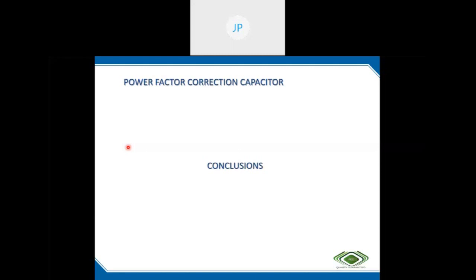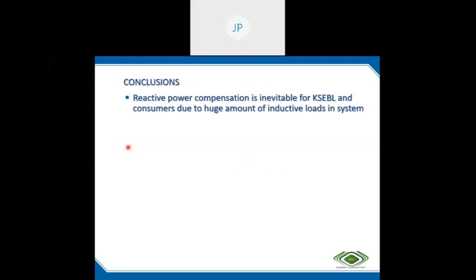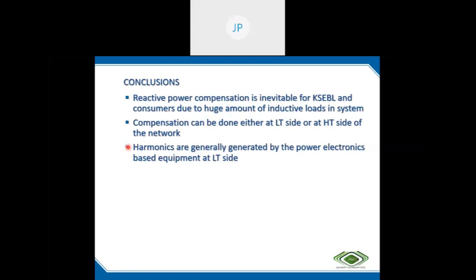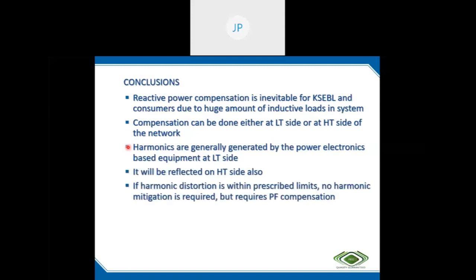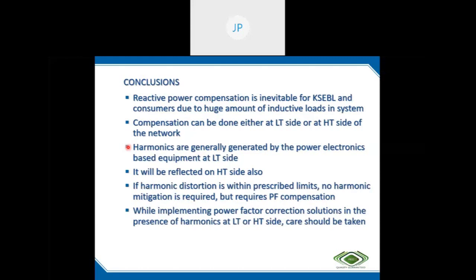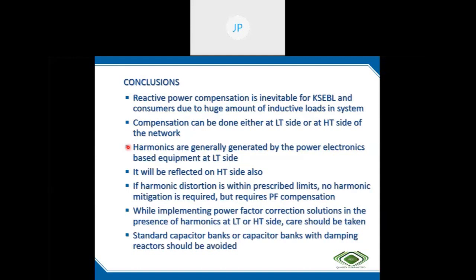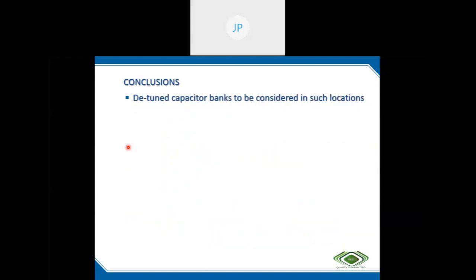Our conclusions are: reactive power compensation is inevitable for KSEB and the consumers due to the high amount of inductive loads in the system. Compensation can be done either at the LT side or HT side of the network. Harmonics are generally generated by power electronics based equipment at the LT side, and will be reflected on the HT side also. If harmonic distortion is within prescribed limits, no harmonic mitigation is required, but power factor compensation is. While implementing power factor compensation in the presence of harmonics at the LT side, we have to take extreme care. Standard capacitor banks or capacitor banks with damping reactors should be avoided in such situations. Detuned capacitor banks are to be considered.